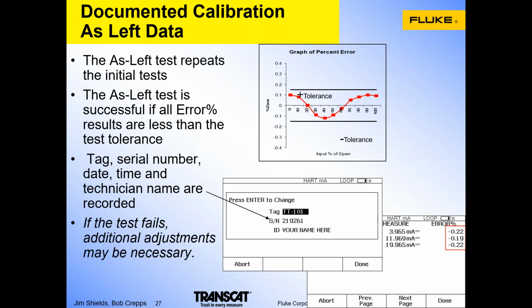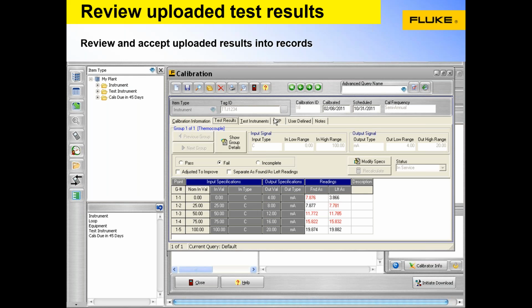And if we take a look at the graphing of the measurements versus the test tolerance, a passing as left would have those measurements well within the test tolerance, indicating that the test was successful. Once the calibration is completed, the results are uploaded back in the calibration management software, accepted and reviewed. And in this instance, we see a record where both the as found and the as left failed. So this is an indication of a device that was not able to be adjusted and would perhaps need to be replaced.